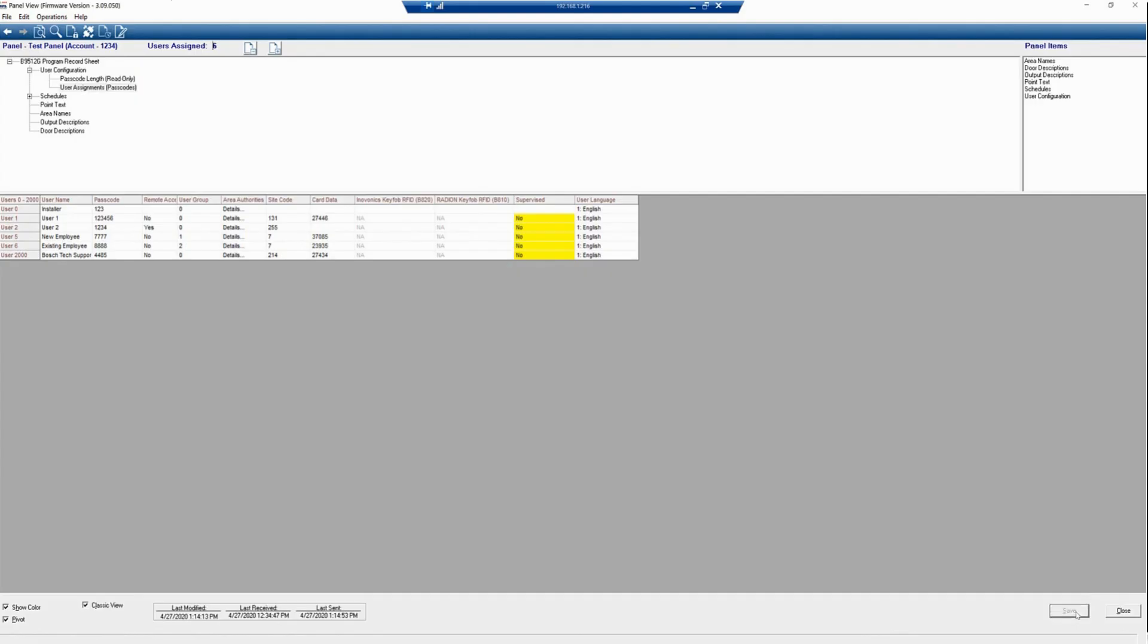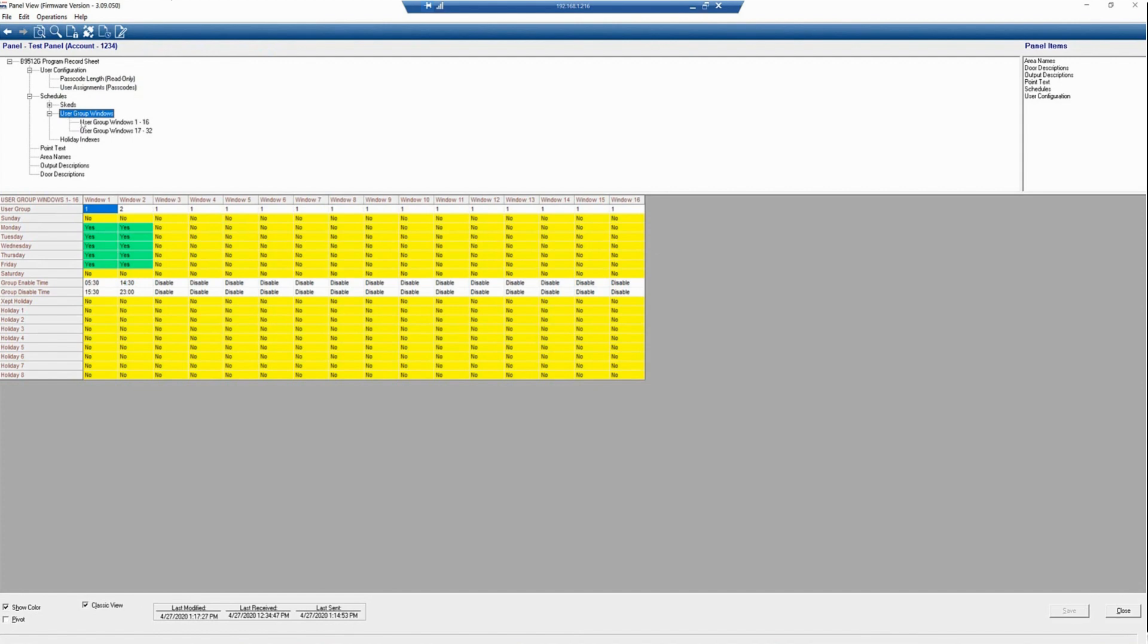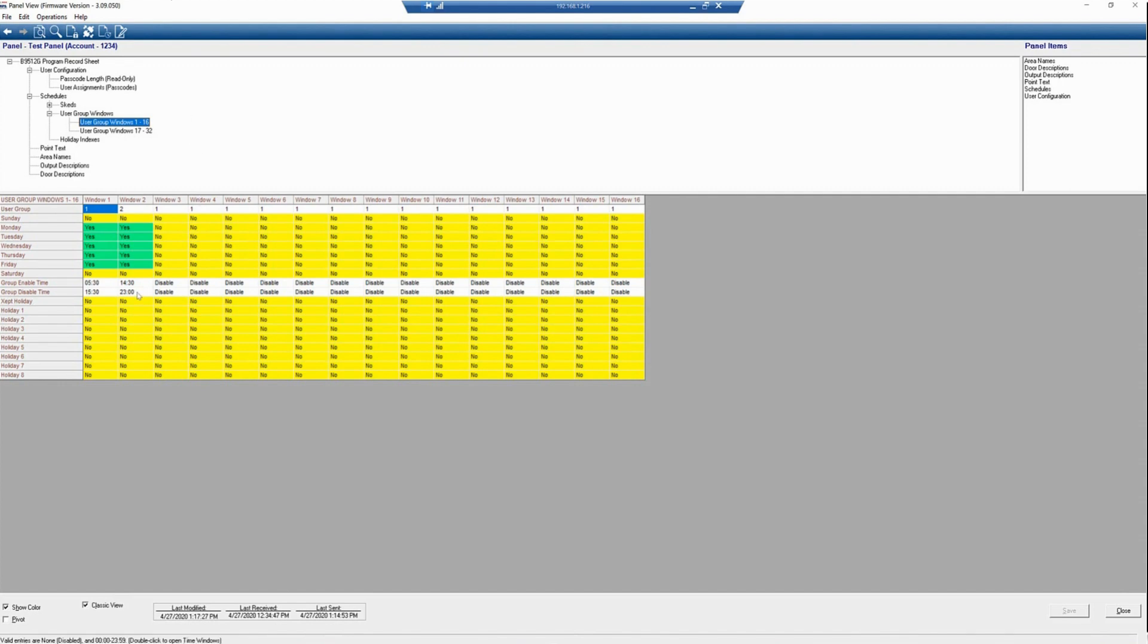Next, we're going to go to Schedules and see how the user groups are set up. We have two user groups set up, one in Window 1 and one in Window 2. Both user groups have access Monday through Friday. However, User Group 1 has access from 5:30 a.m. to 3:30 p.m., and User Group 2 has access from 2:00 p.m. to 11:00 p.m. This is just for this particular application. You could have multiple user groups and multiple user group windows.